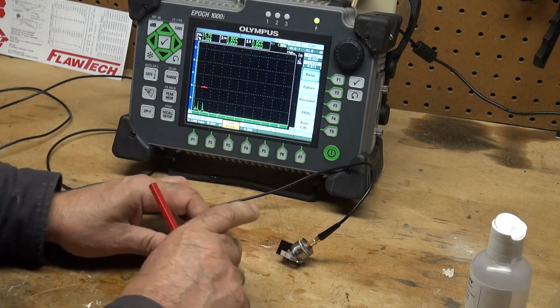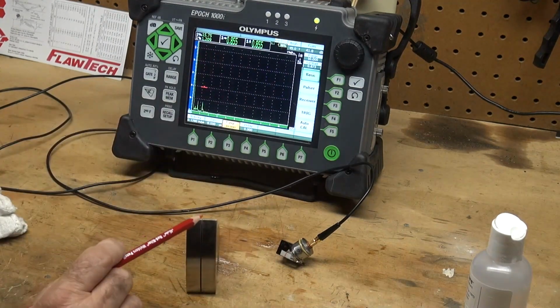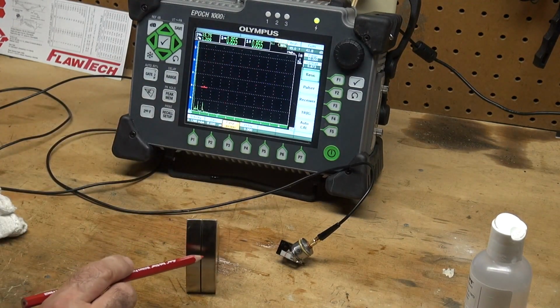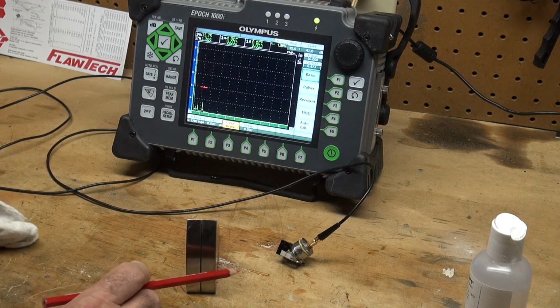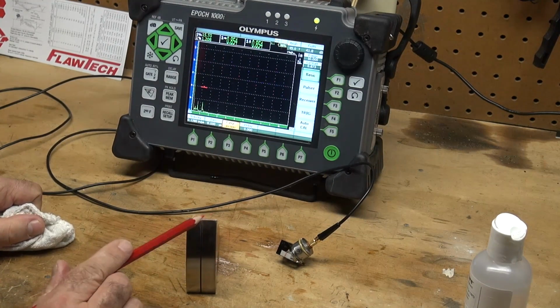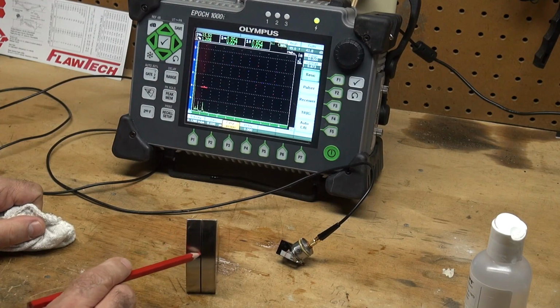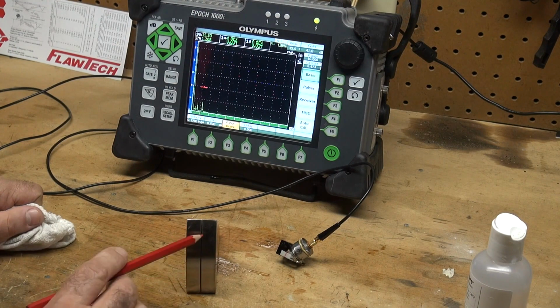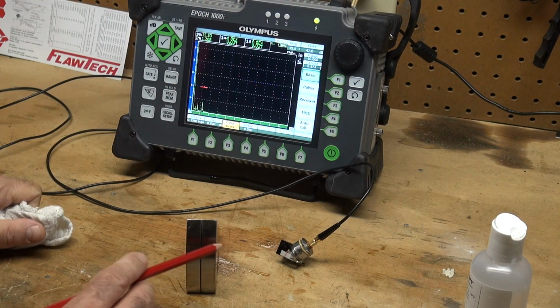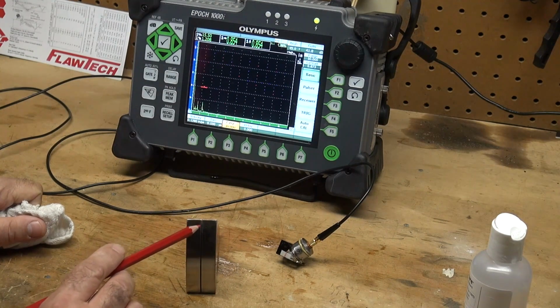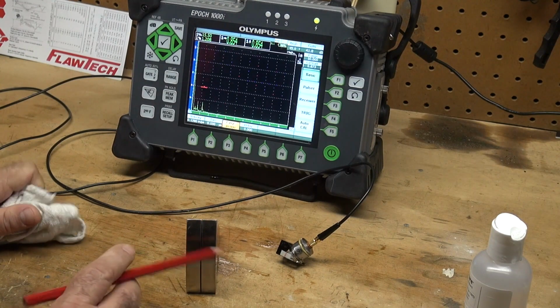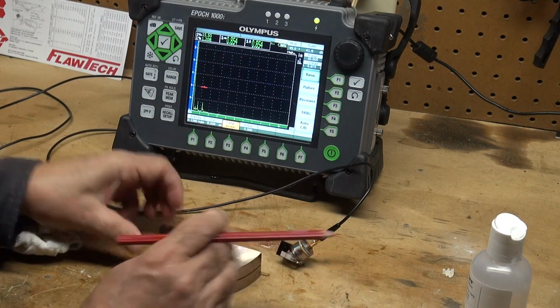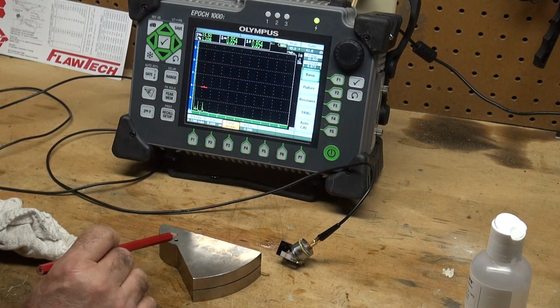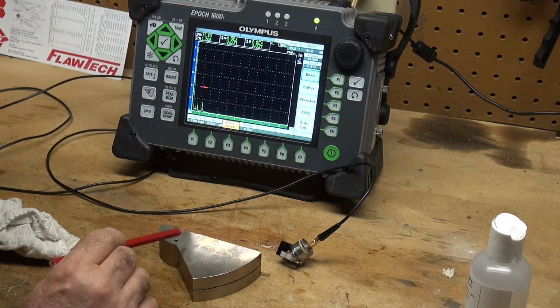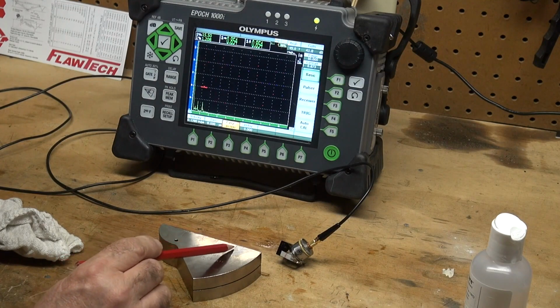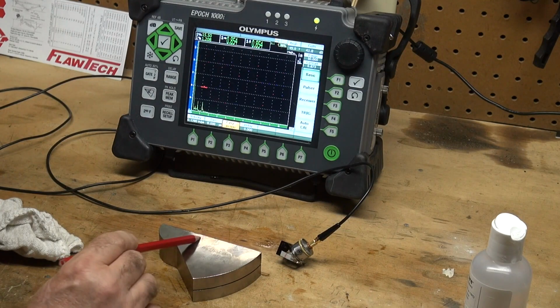Another thing that's interesting about this block is that on the edge with the 3-inch radius, there is a 1/32 inch wide groove that is cut 0.375 inches deep, and we use that for our reference. And also I can measure the angle of my transducer shooting at this hole, and it's 45 to 70, looks like 75 degrees.